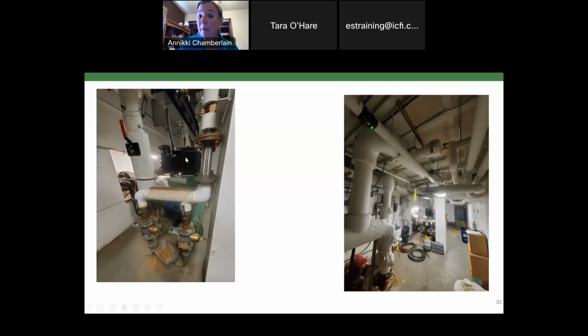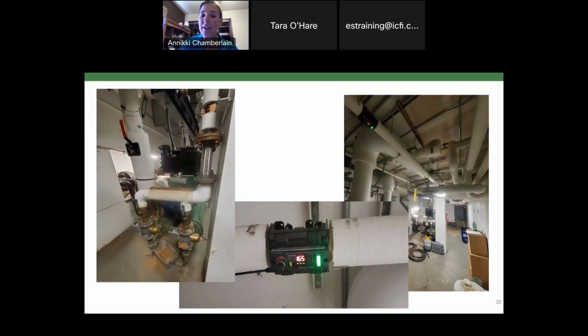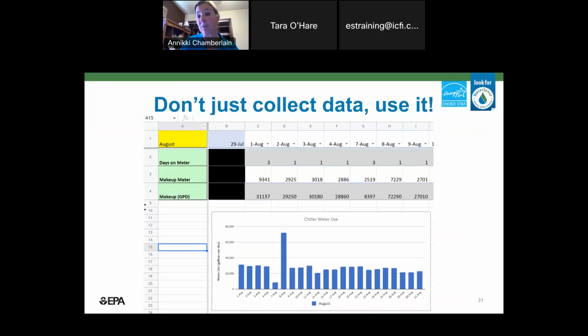So to help this property, we basically installed a meter on the makeup, on the water supply. So if the chillers are not running, but that water is flowing, you can easily look at that and be like, boom, I got a problem. It's visible, it's a clamp-on meter, so no installation. But we also want to find routines that identify problems and inform us of long-term trends. So we set him up on a Google Docs on his phone. He goes by, he selects the day, automatically updates the number of days on the meter, puts in the meter read, and so boom, we have our gallon per day use. So not only can we identify immediate problems, but we can identify anomalies from day to day.